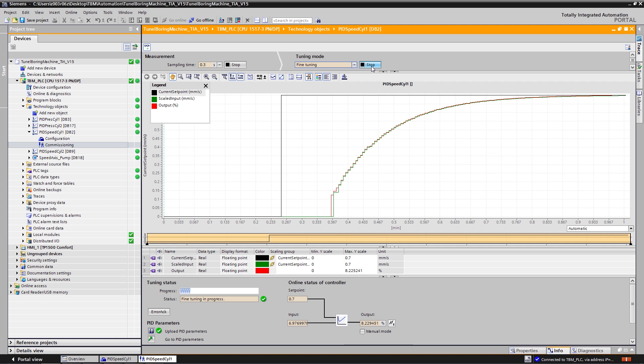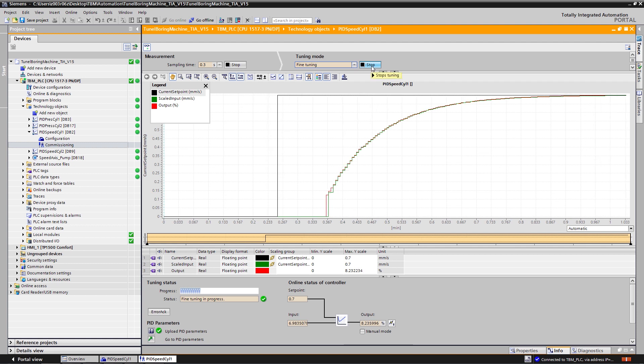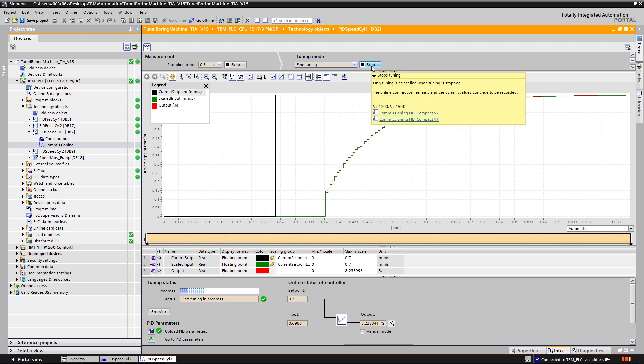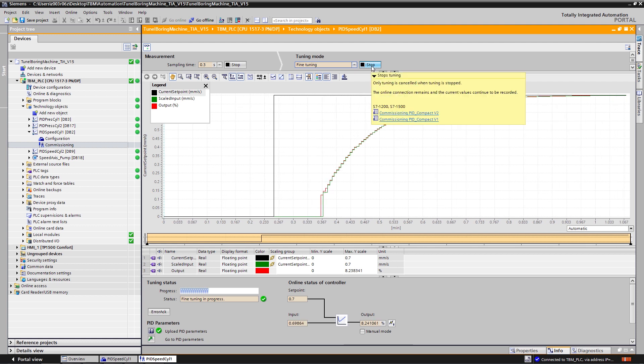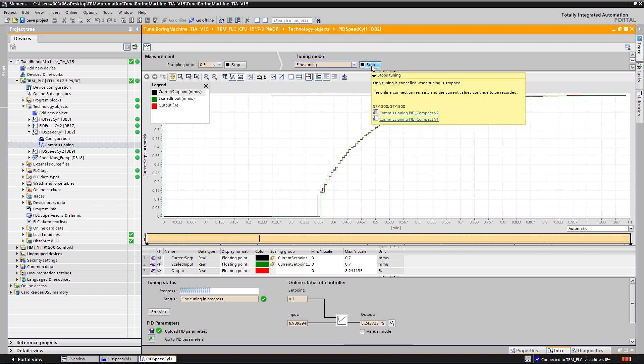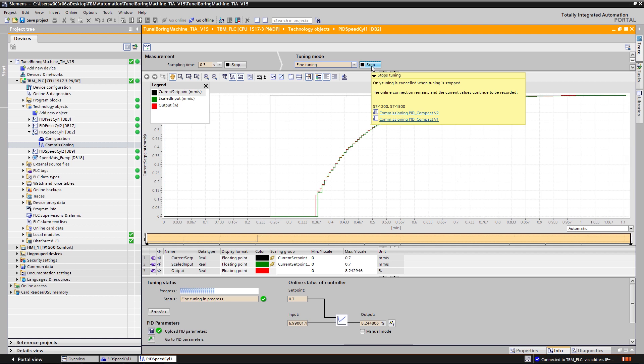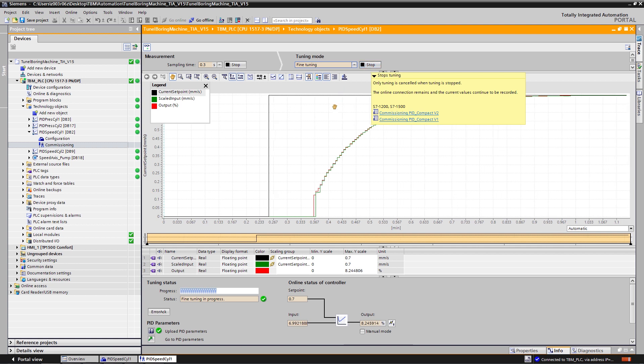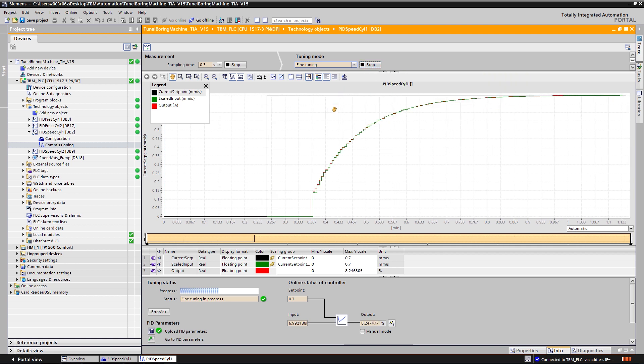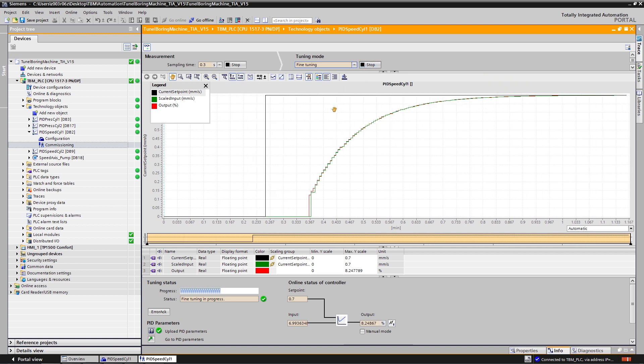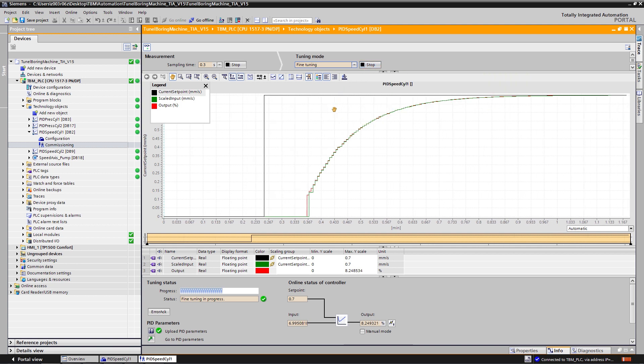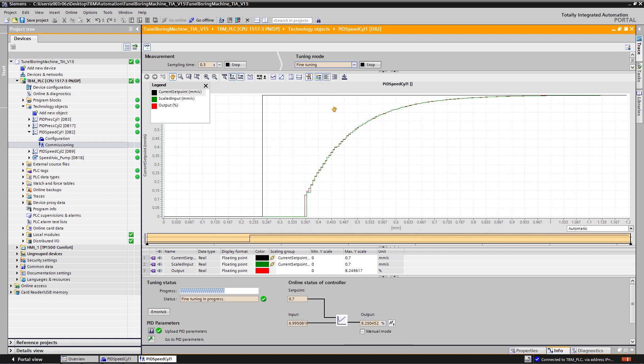Now TIA Portal will send oscillations to my system and measure the reaction of my system. Based on this information, it will calculate the new optimized PI parameters.